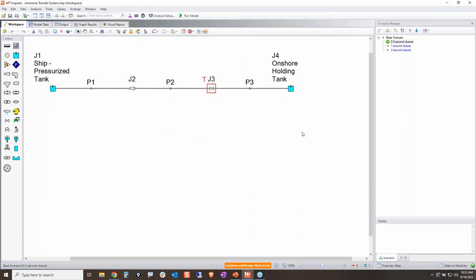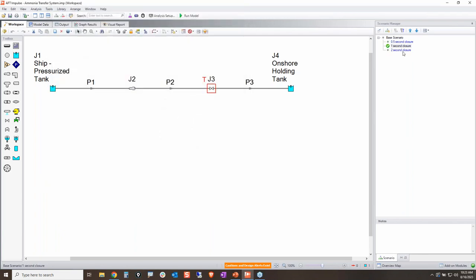The piping system has a reservoir representing the ship tank pressurized at 250 psi gauge, discharging to an onshore holding tank also at 250 psi gauge. There's an 8-inch diameter pipe 100 feet long off the ship, then 10-inch pipes of 300 feet and 150 feet. I'm going to iterate on valve closure time frames, starting with the assumption of closing the valve linearly from 1000 Cv to zero in 0.5 seconds, then trying 1 second and 2 seconds.